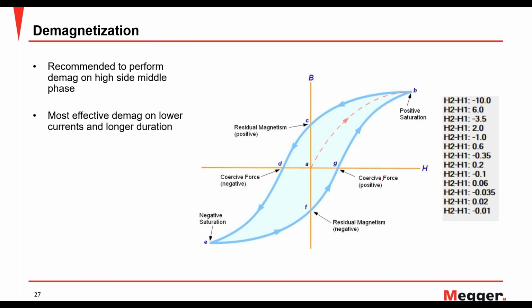This might remind you of your university or school days. This was a BH curve that everyone studied in their university education. This is how it's actually going up, and it's going to move the residual magnetism positive, negative, and then it's going to move back to 0 in that case. These are the current magnitudes being applied by the test equipment: negative 10, positive 6, minus 3.5, 2, minus 1. So these are different voltages, currents that are being applied. And if you notice, those are only being applied between H2 and H1.